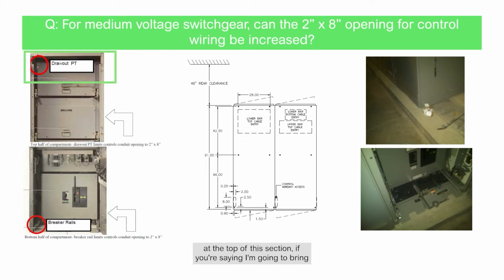Looking at the top of this section, if you're saying I'm going to bring the wires into the 2 by 8 inches opening on the top of the medium voltage section, you have the same issue except with the draw-out potential transformer, draw-out PT. If you're trying to pull out that draw-out PT and you expanded a wire entry point wider than a 2 inches width, then you would be interfering with being able to open up that draw-out PT.